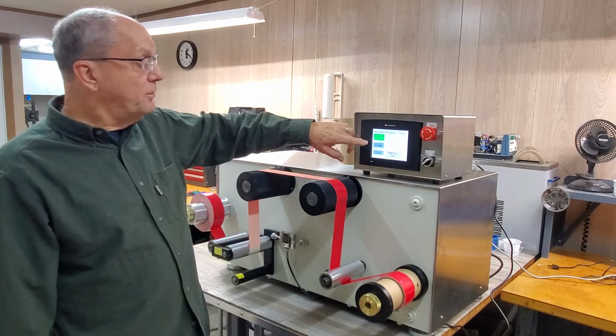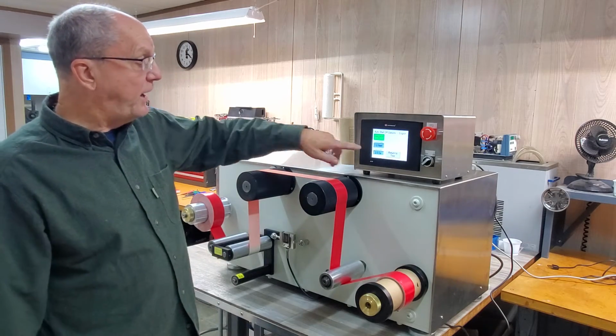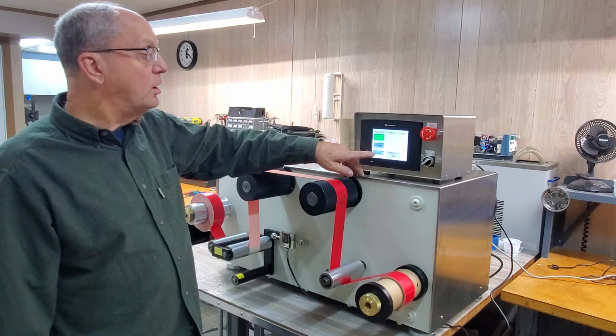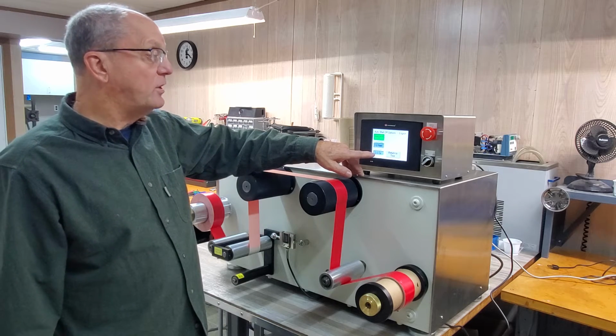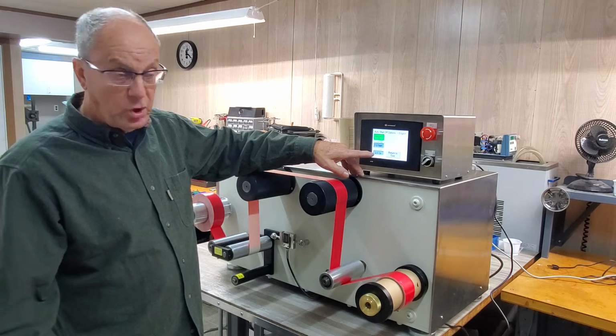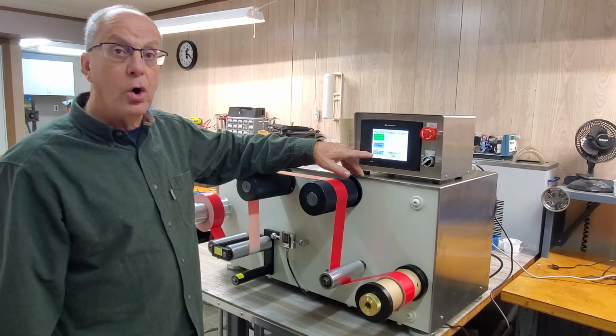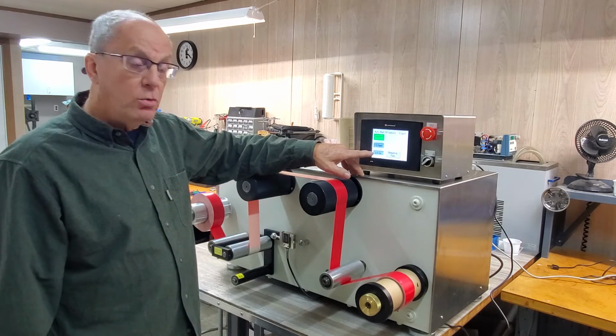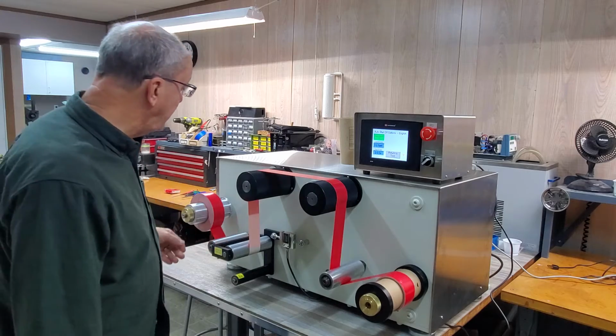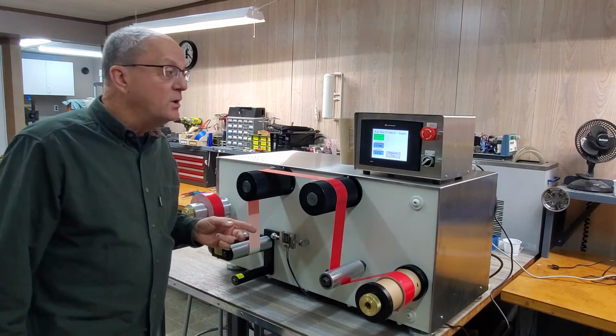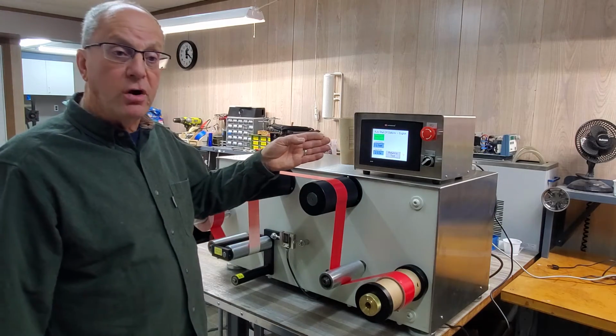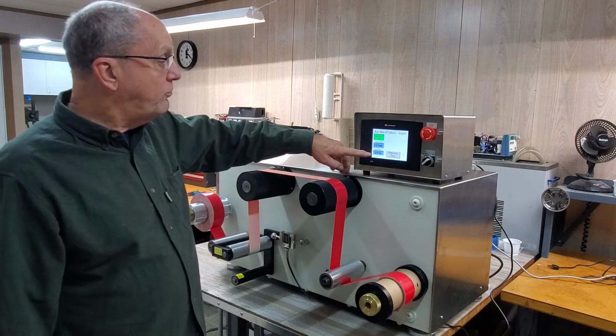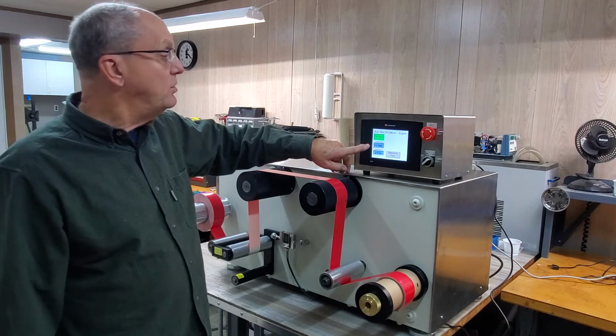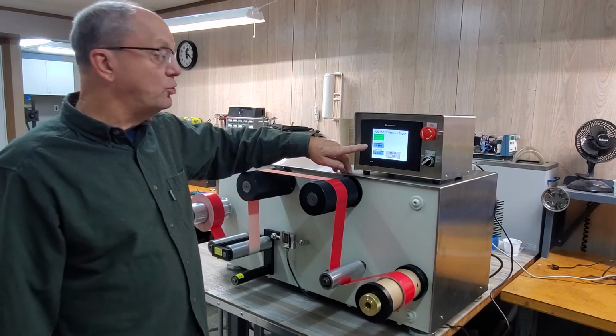Now what we have here is, as we run the test, when our tension gets less than 2 ounces, like if we're at the end of the roll, this thing is going to automatically terminate the test. Well, if you think about it, when we start the test, if we have slack in the roll, this thing's going to shut off immediately. So we have what's called shut off inhibit, which I have set in this example to 1 foot.